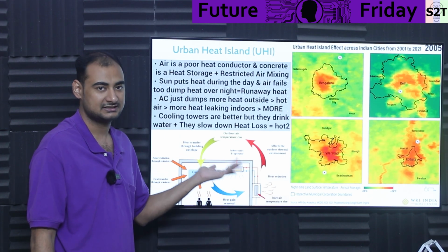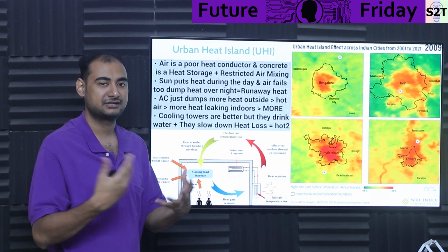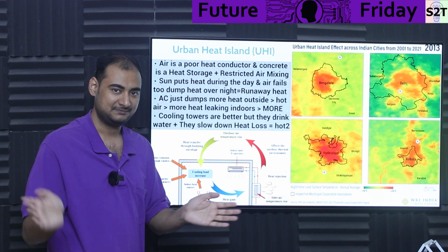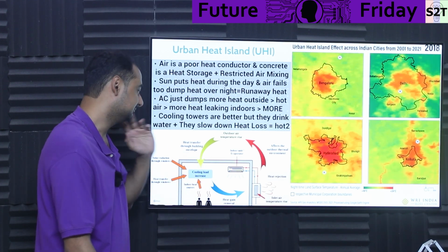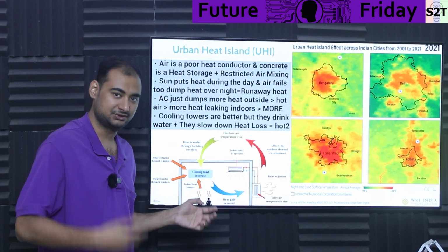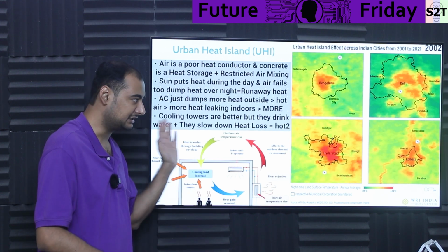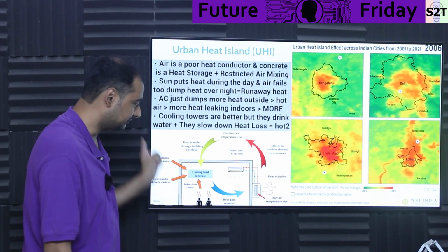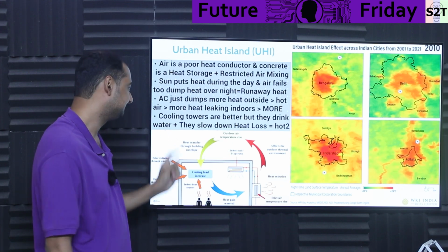So the leakage, the leak heat coming inside, goes up exponentially, meaning you reach a point where it's basically inherently trying to run a refrigerator whose door is open. So it can't work. What do you do when it can't work? You put more energy, more load into it, and the cycle continues. So it really turbocharges its own demise.